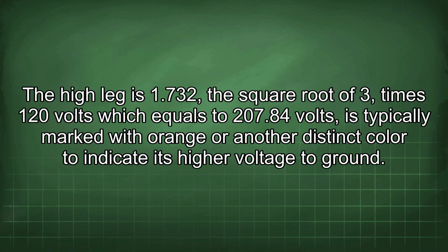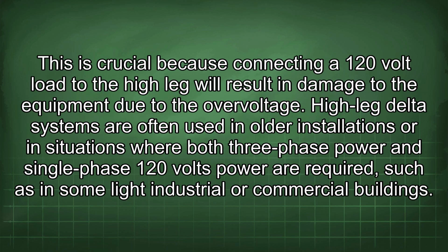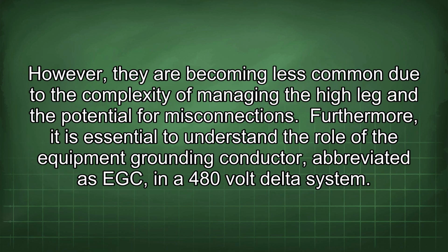The high leg voltage is 1.732, the square root of 3, times 120 volts, which equals 207.84 volts. It is typically marked with orange or another distinct color to indicate its high voltage to ground. This is crucial because connecting a 120 volt load to the high leg will result in damage to the equipment due to the overvoltage. High leg delta systems are often used in older installations or in situations where both three-phase power and single-phase 120 volts power are required, such as in some light industrial or commercial buildings. However, they are becoming less common due to the complexity of managing the high leg and the potential for misconnections.